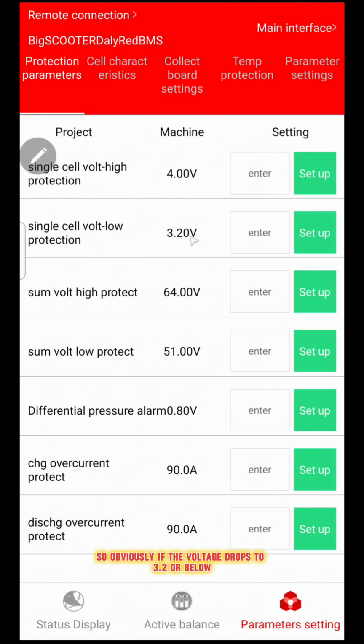So obviously if the voltage drops to 3.2 or below, it will cut out the battery pack and stop working. I've got the sum low voltage protect at 51 volts, so that's the sum of the 16 strings. Differential pressure alarm, so you get an alarm come up on the display showing the voltage difference between strings if it's greater than 0.8 of a volt.